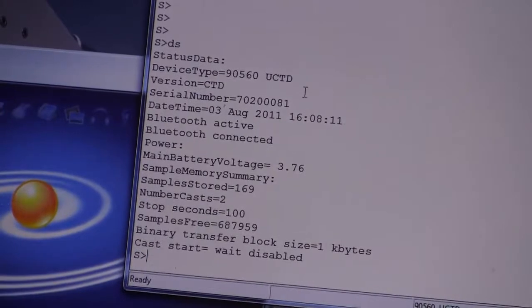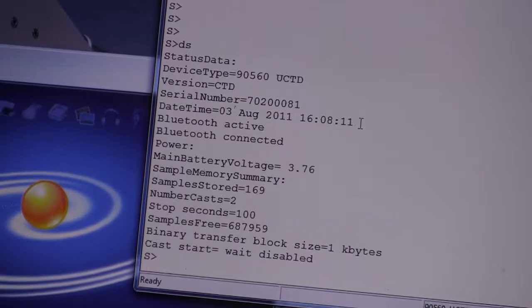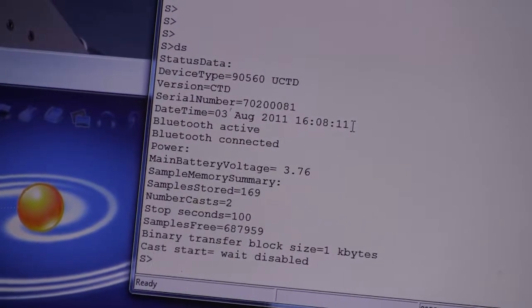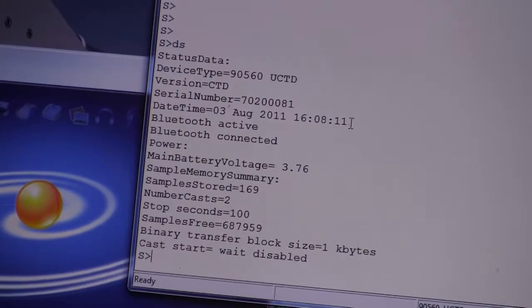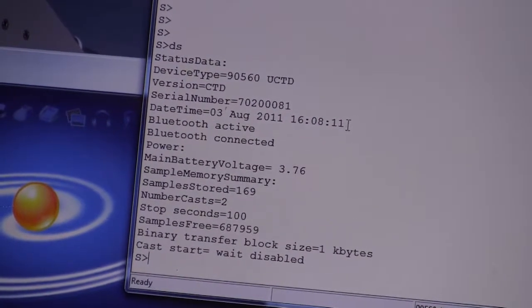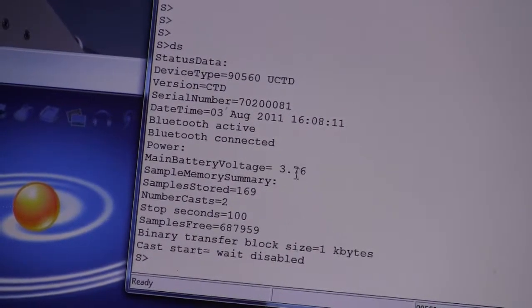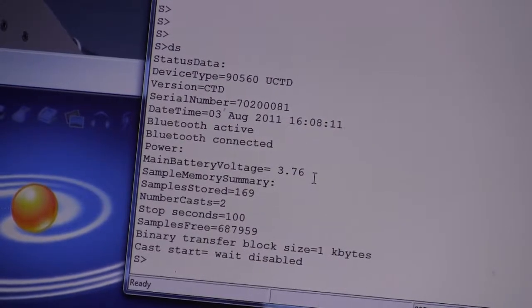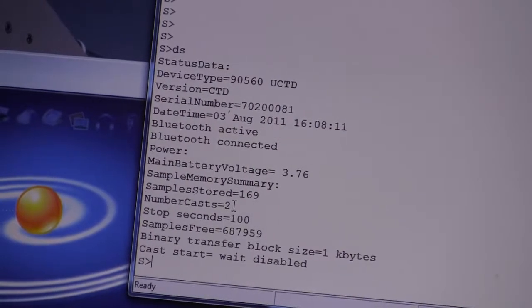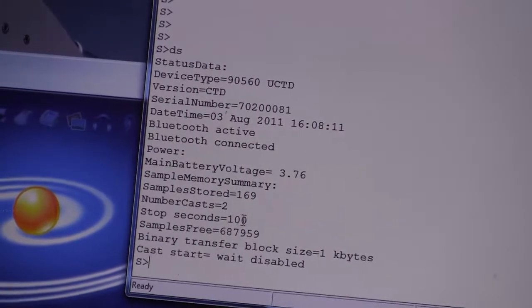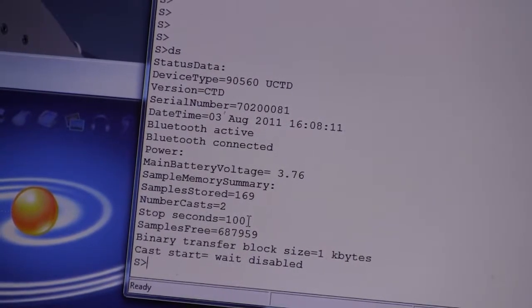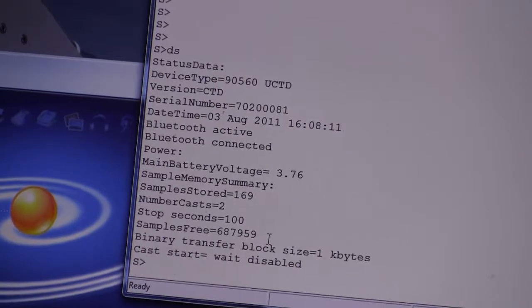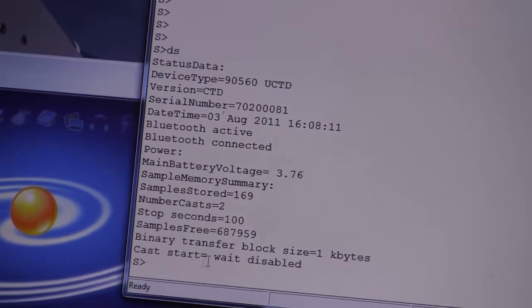First, the serial number up here. Then in the line underneath, it gives you the date and time of the real-time clock on the probe, which is important for synchronization with the GPS location. It also gives you information about the battery voltage. This one is 3.76, so this is a well-charged probe. The number of samples that are currently stored on the probe. Also the number of profiles stored on the probe. Currently how long the probe will record when the data acquisition is activated. How much free memory is on the probe. That's pretty much the main information.